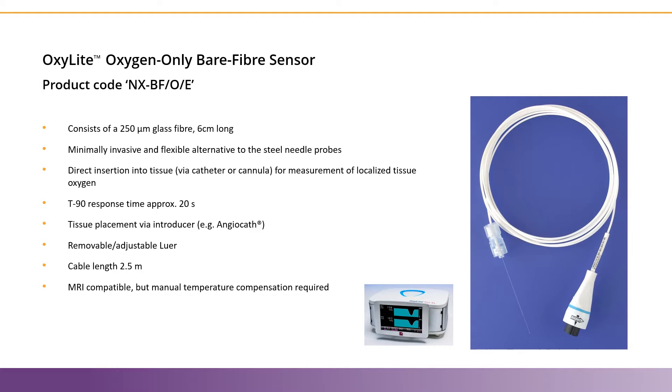It's placed with an introducer, like an angiocath, and can be placed in virtually any tissue. The removable Luer connector means that you can use it with standard ports, like in cerebral applications, or for more acute studies like muscle, skin, or tumor applications. They can be cleaned with 70% alcohol, and the white coiled cable you see in the photo on the right is approximately 2.5 meters long.